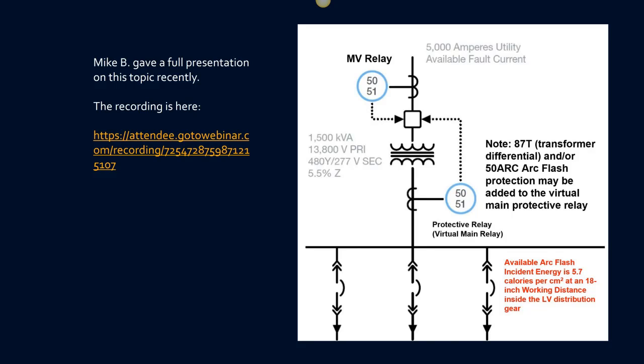So we eliminate that 2,000 amp physical main, and we replace it with a set of CTs, one on each phase, an overcurrent protective relay, which trips the primary device. Now, clearly, in order to make this space-saving alternative work, you need to own the transformer. If the utility owns the transformer, this is not an option that can be implemented.